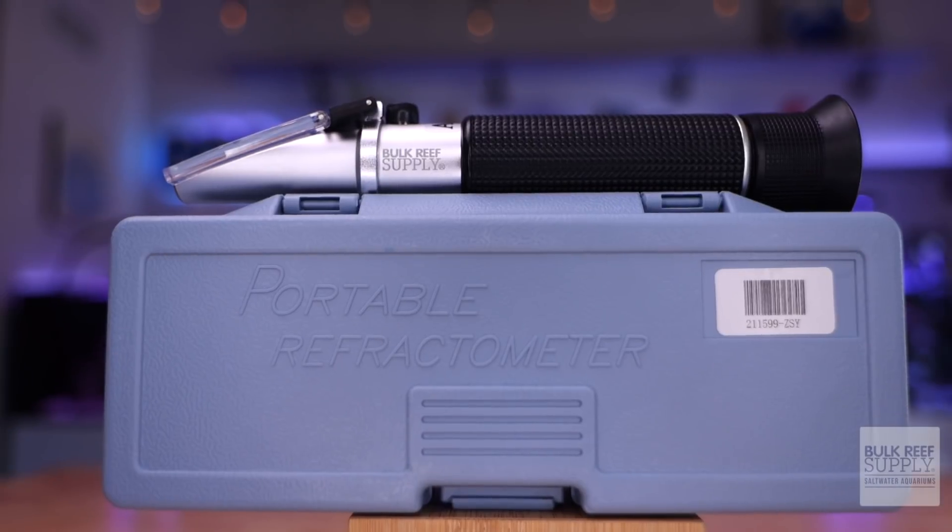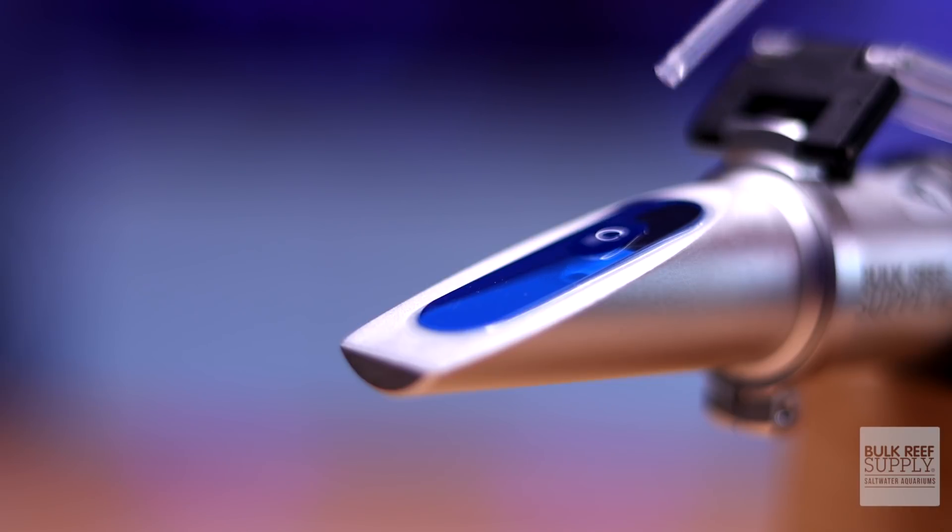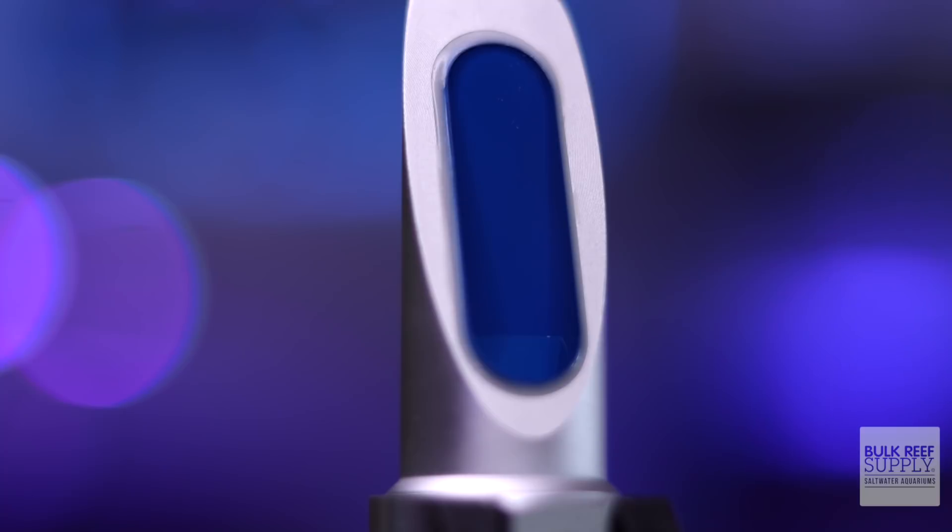A refractometer uses the refraction of light in water to approximate salinity. Changes in the concentration of salt affect the refraction of light. A refractometer measures how much refraction is occurring and displays the results on a graduated scale. So a refractometer merely measures light refraction. When measuring seawater, we assume the more refraction there is, the more salt is in the water, allowing us to approximate salinity.